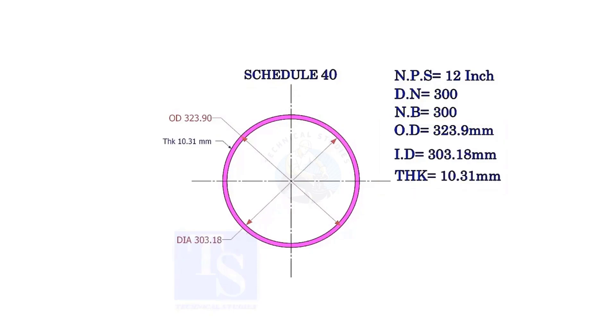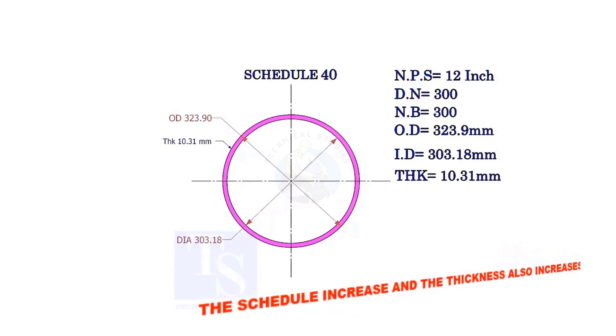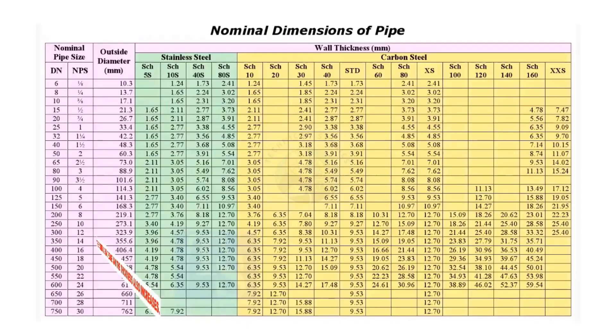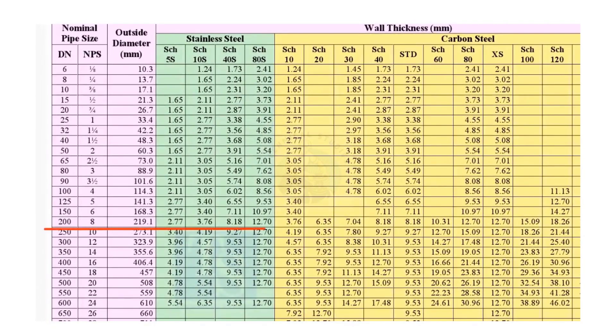Let us check the dimensions of the same size pipe with a higher schedule. As the schedule increases, the OD remains constant, the ID decreases, and the thickness increases. Compare the thickness of an 8 inch pipe in the chart — you can see the thickness increases as the schedule increases.